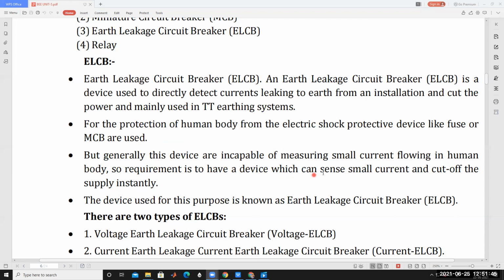MCBs and fuses are also used to protect human bodies, but for a small amount of leakage current they do not respond. Because of that, ELCBs are generally used. ELCBs cut off the supply instantly. This device is capable of measuring the small current flowing in the human body, and it is used for the purpose of detecting earth leakage current.